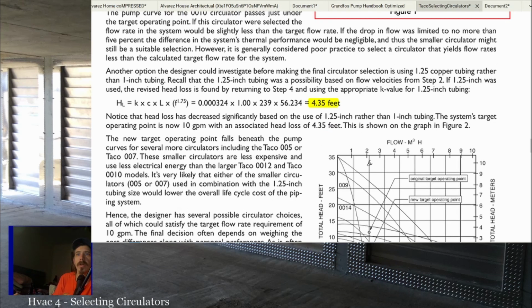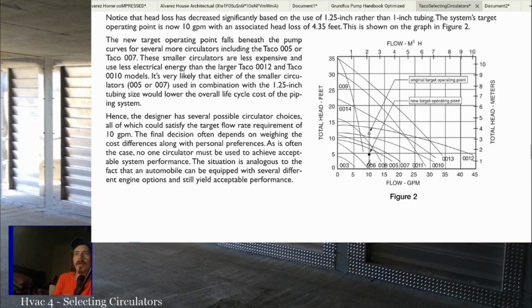All right. So the head loss decreases significantly just one pipe size up, and you're still operating at 10 GPM, but now you've got a head loss of 4 feet. So you can replot that point on your graph, and you'll be right here instead. I think I got an arrow. Nope. So that's the second point, and that's the first point we had, right? On the second point, we can see that we can use a 005 or a 007. So if you look at it, the 007 is here, which is a very common pump, and the 005 is here. Dang it.